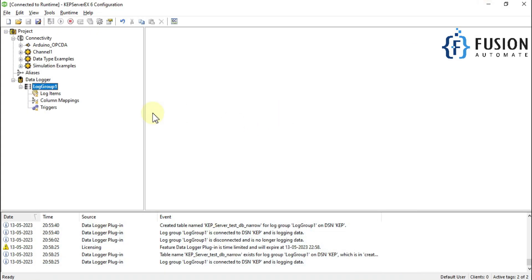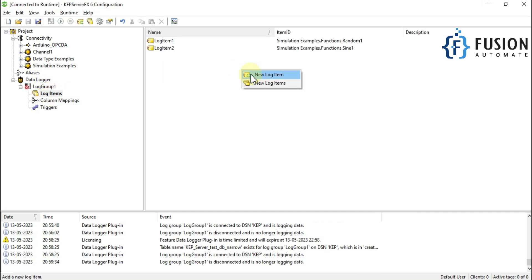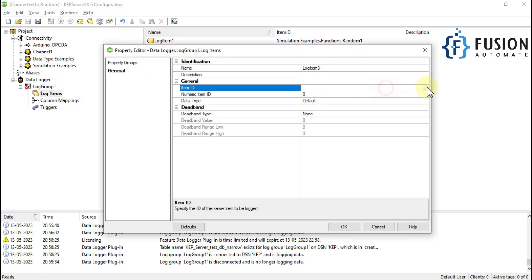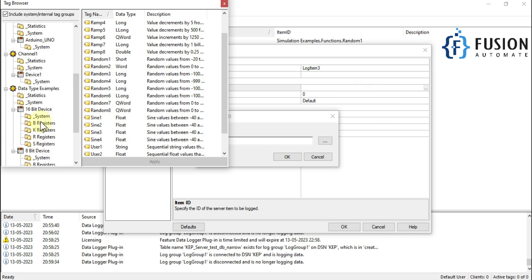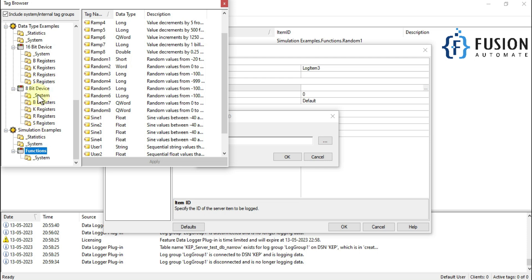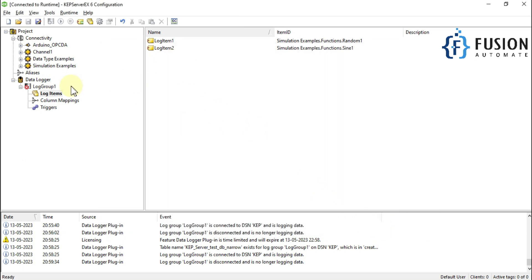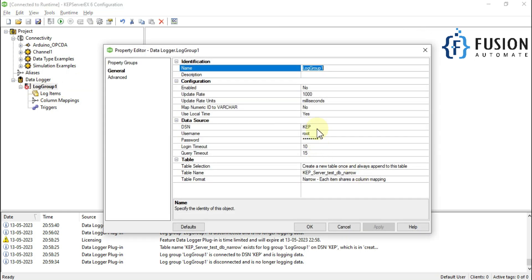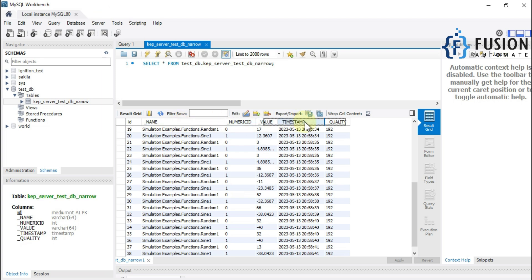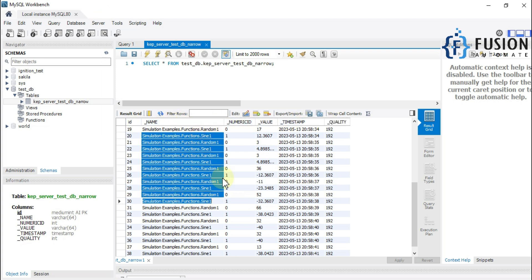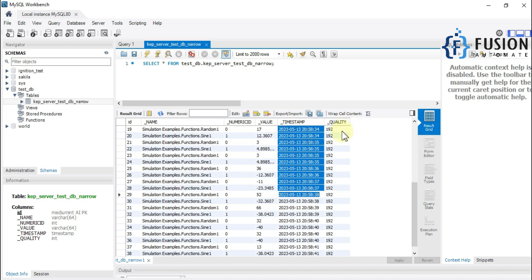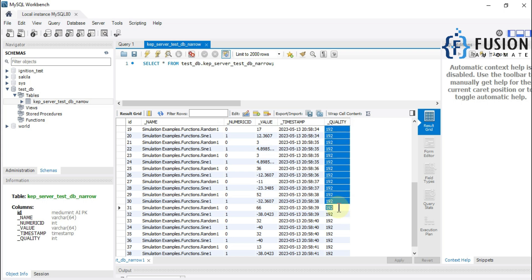Whether your data comes from the shop floor or is random values, it works the same way — you simply select your tag from the available connections. If you add a new log item, all your connections — OPC, Modbus, PLC — all tags will appear and you can select them. Now regarding the Narrow table format: it has these columns — one for tag name, one for numeric ID of the tag, one for value, one for timestamp, and one for quality.